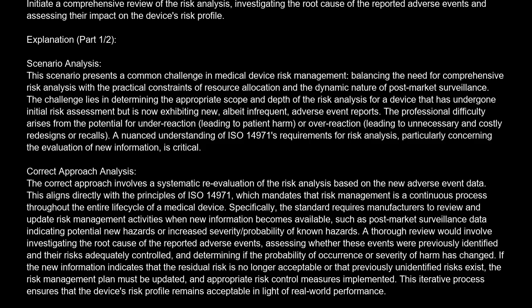A thorough review would involve investigating the root cause of the reported adverse events, assessing whether these events were previously identified and their risks adequately controlled, and determining if the probability of occurrence or severity of harm has changed. If the new information indicates that the residual risk is no longer acceptable or that previously unidentified risks exist, the risk management plan must be updated and appropriate risk control measures implemented. This iterative process ensures that the device's risk profile remains acceptable in light of real-world performance.